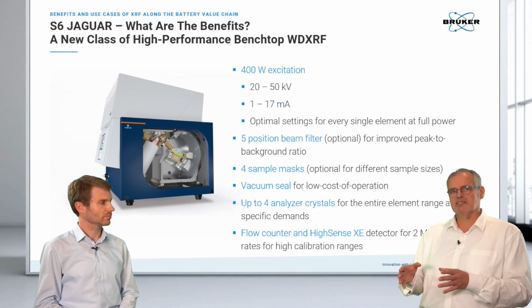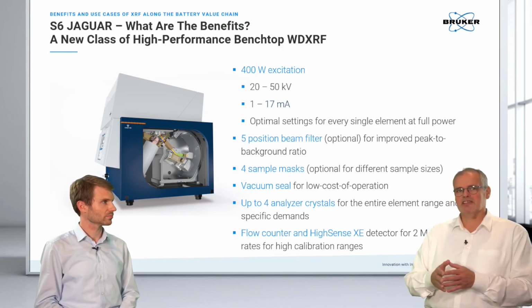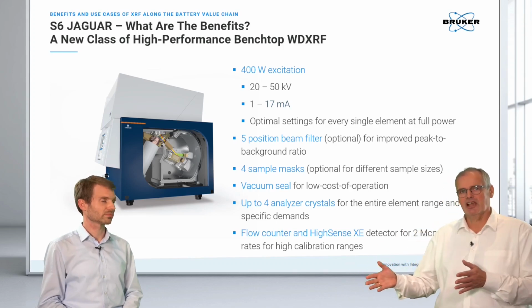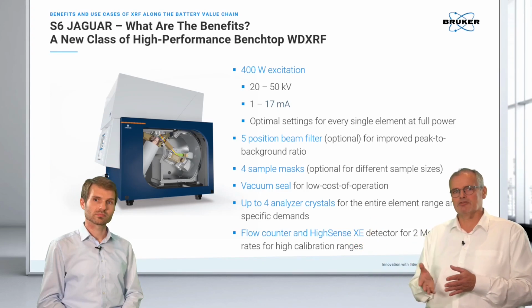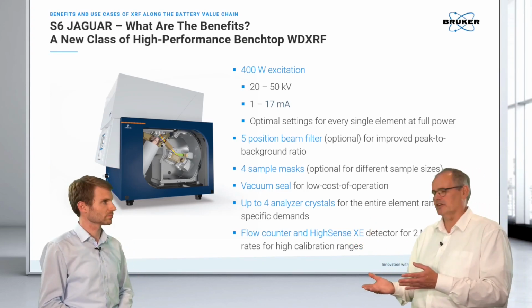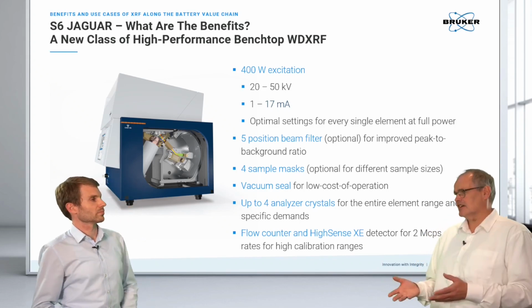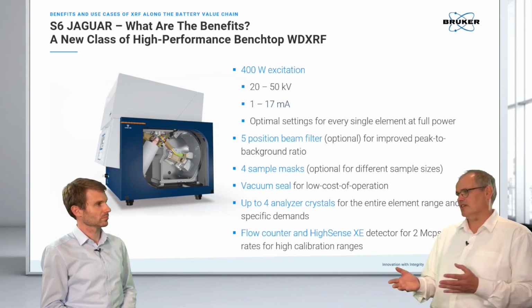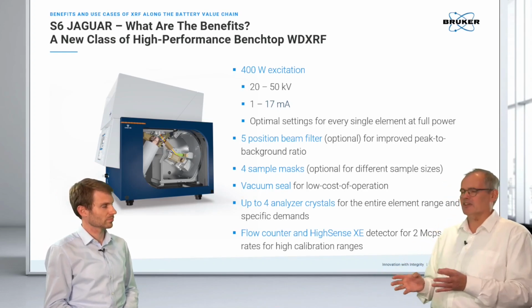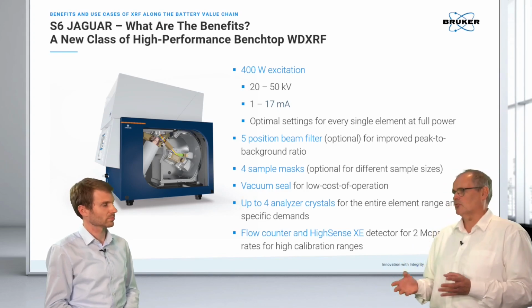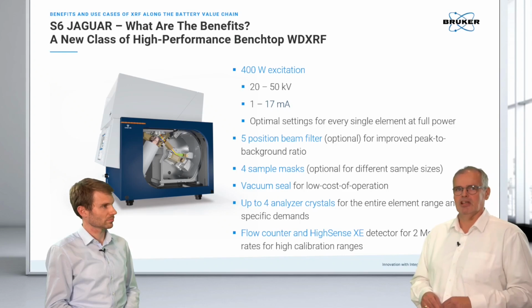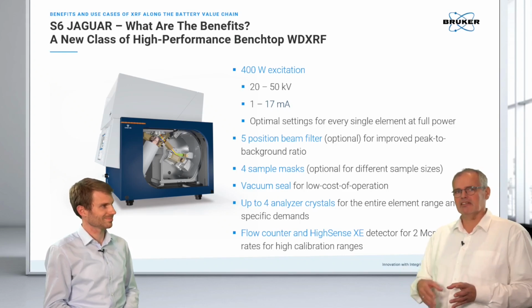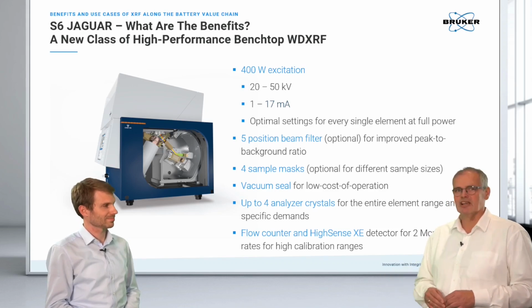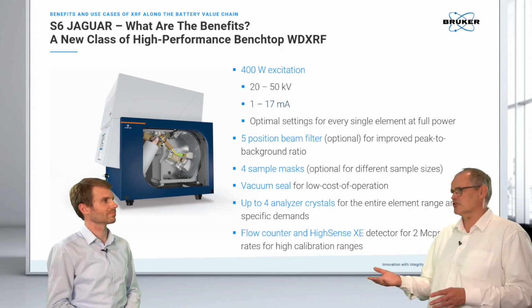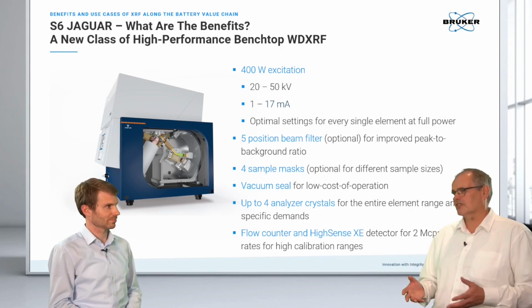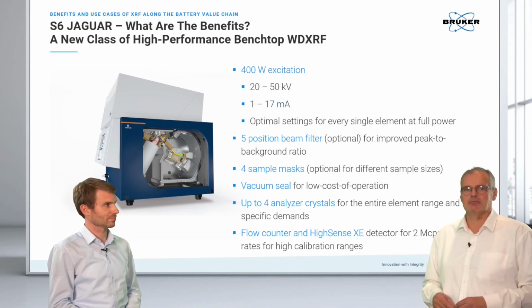So what happens here is that we have analyzer crystals which separate the incoming beam into the different energies. And then we have two detectors which travel to the position where this energy needs to be recorded. With the flexibility in the excitation voltage from 20 to 50 kV and 1 to 17 milliamps, we can fine-tune the excitation and the detection of each element, which then leads to a very nice analytical power. This sounds a little bit complicated, but the instrument does the settings by itself. It knows which crystal to use and which position to travel to. So this is all automated. The only thing we need to do is to tell it, hey, those are the elements I'm interested in.